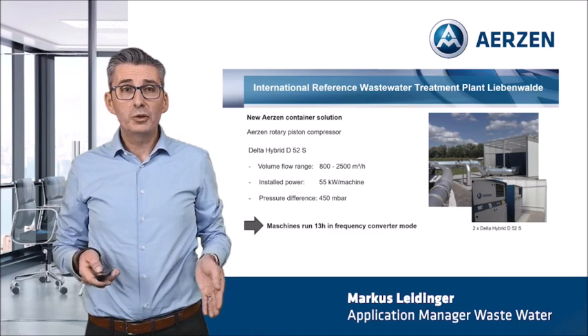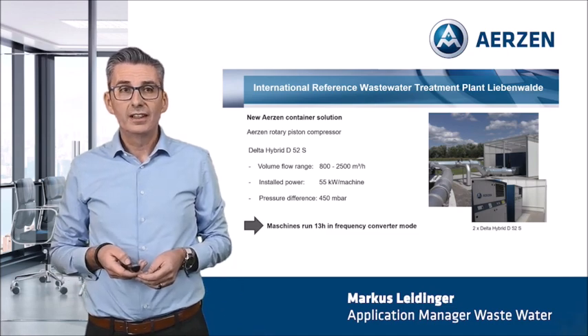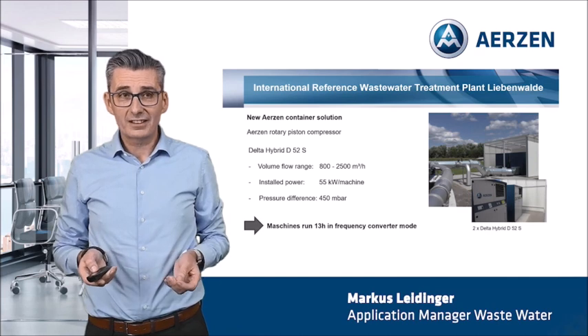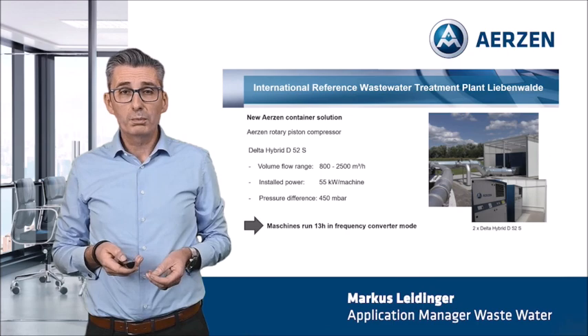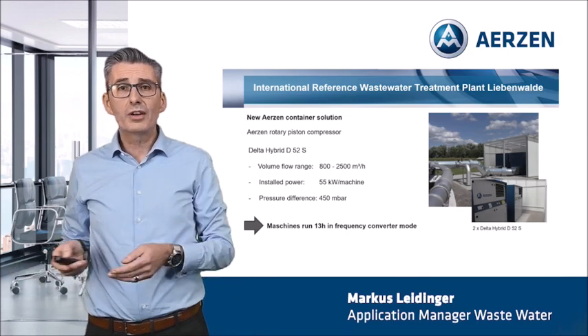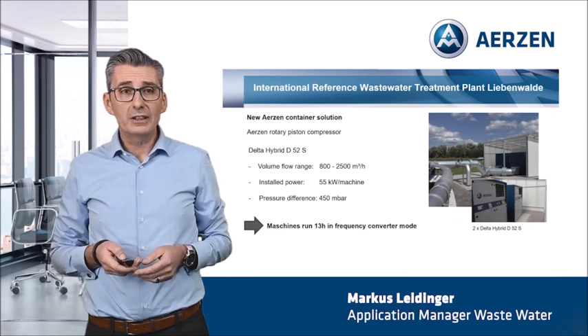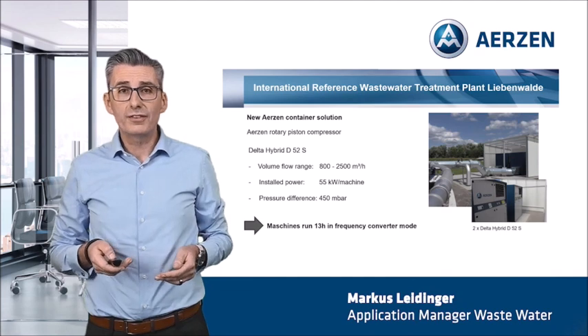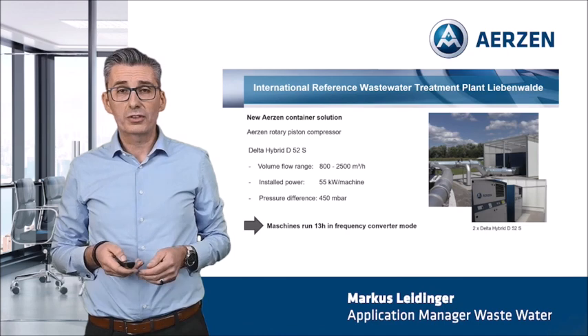Now let's take a look at the performance data of the new Aerzen container solution. In our container, we packed two Delta Hybrid D52 machines. Both machines have exactly the same performance data. The machines are configured for a volume flow between 800 up to 2,500 cubic meters per hour. The installed power is 55 kilowatts per machine and the pressure difference is only 450 millibar. The machines run in frequency converter mode 13 hours per day.